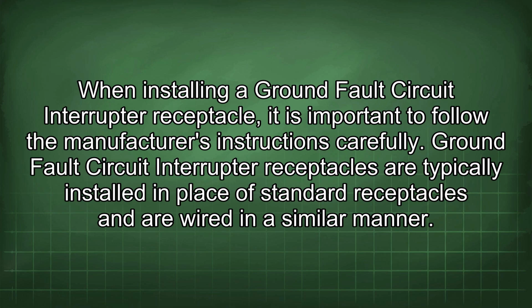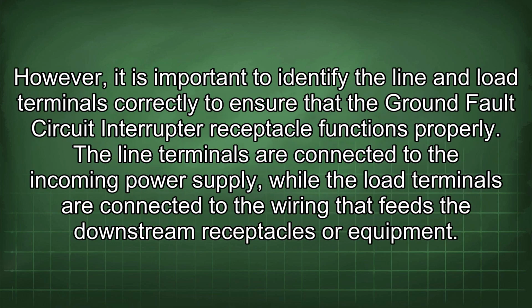When installing a ground fault circuit interrupter receptacle, it is important to follow the manufacturer's instructions carefully. Ground fault circuit interrupter receptacles are typically installed in place of standard receptacles and are wired in a similar manner. However, it is important to identify the line and load terminals correctly to ensure that the receptacle functions properly. The line terminals are connected to the incoming power supply, while the load terminals are connected to the wiring that feeds the downstream receptacles or equipment.